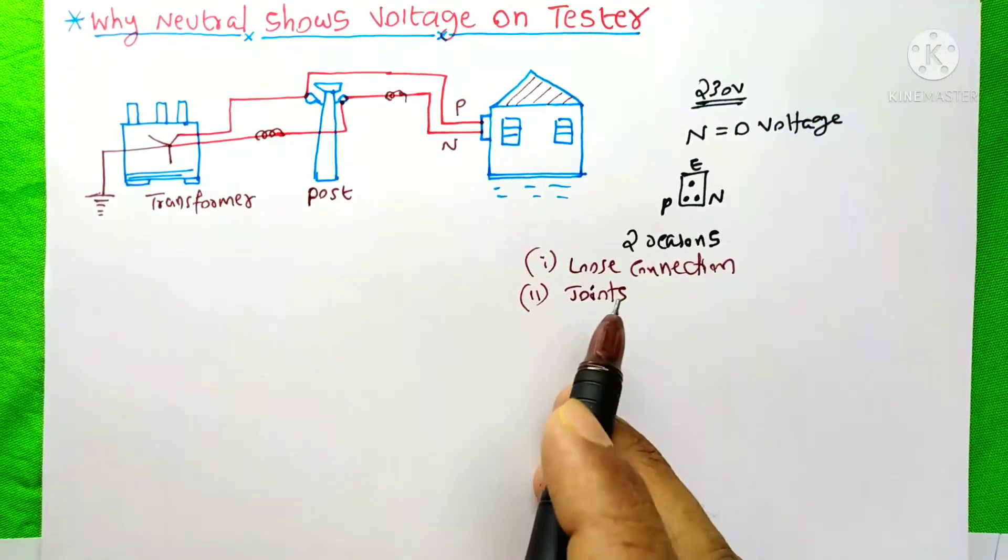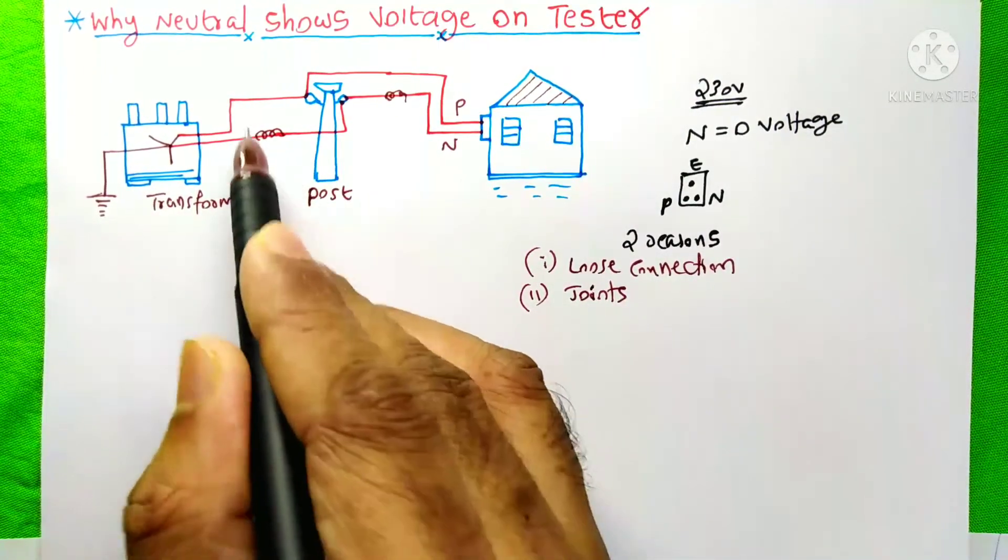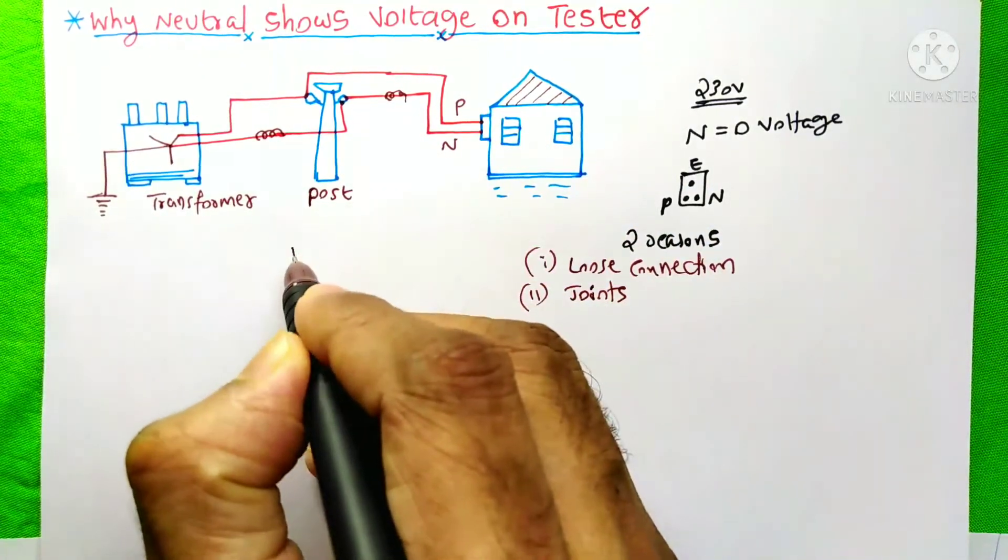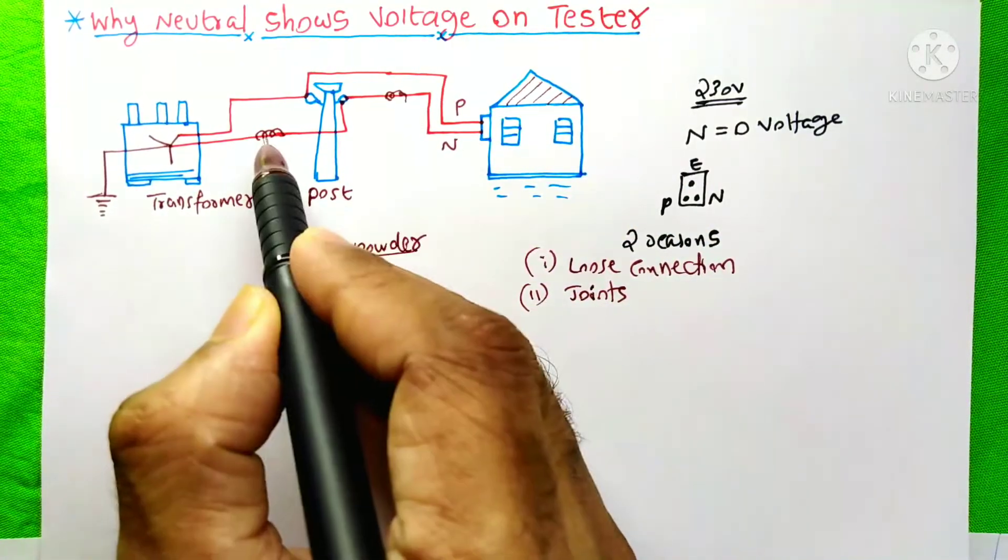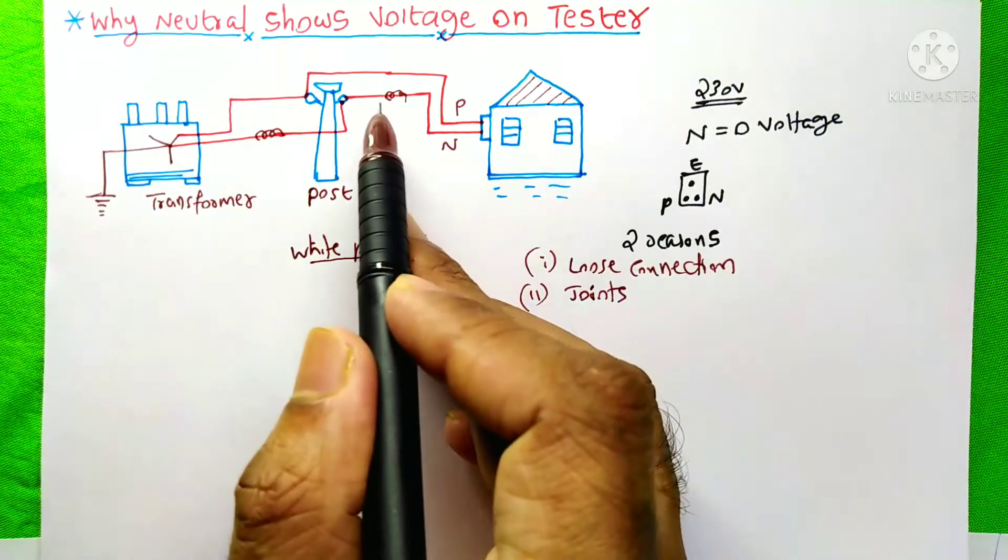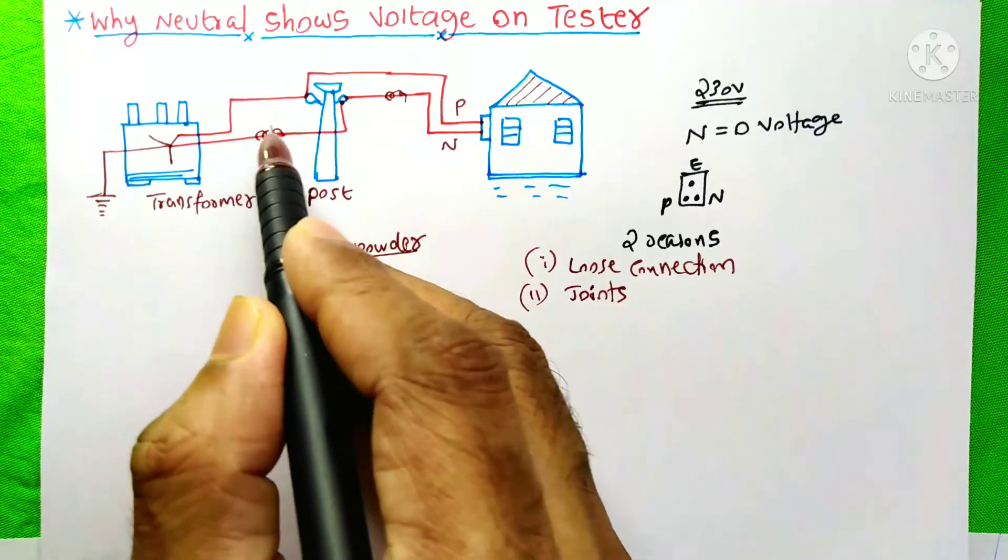During some urgent situations, when technicians made these joints, after some time, a white color powder will be formed on these joints. And due to that, the return current would be blocked by the white colored powder.